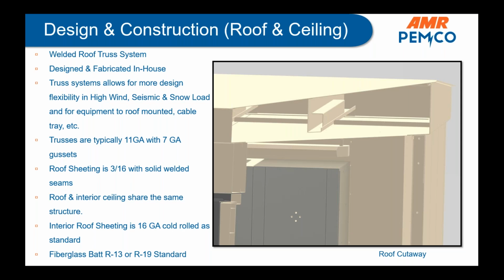We can vary that if we get into roof loads. This roof design cures a lot of ills in the certification process from a seismic and wind load standpoint, and it also allows heavier inherent roof loading. So if you need air conditioning on the roof, resistors, or need to hang cable tray or busway from the ceiling, it gives you a lot more flexibility in your applications than a standard design.